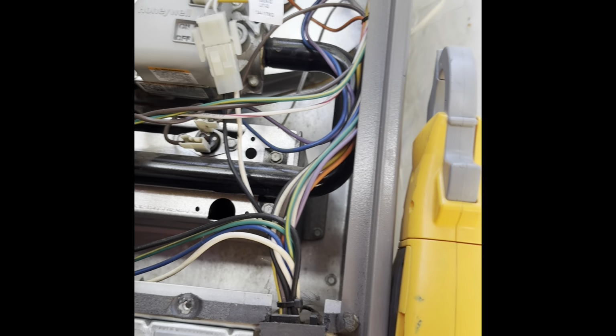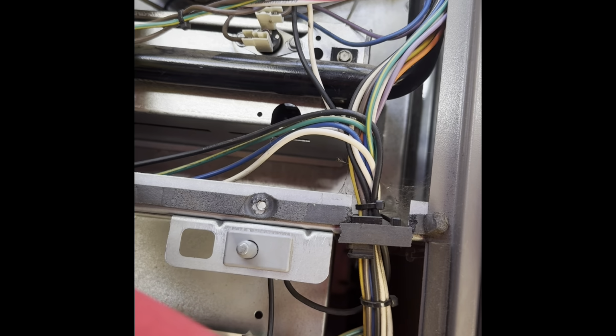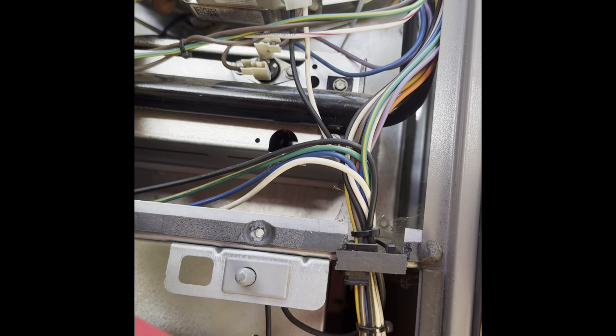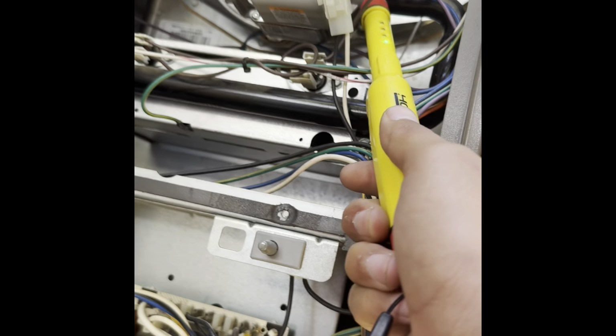One of the main things I like to check is the gas valves. They tend to leak out of the bottom plate. There's a plate at the bottom. Let me show you. I don't know if you can almost see it right there, but that plate. In between the plate, there's a gasket. Over time, the gasket tends to break and cause leaks. So that's the reason why we check to make sure that there's no leaks at the gas valve.